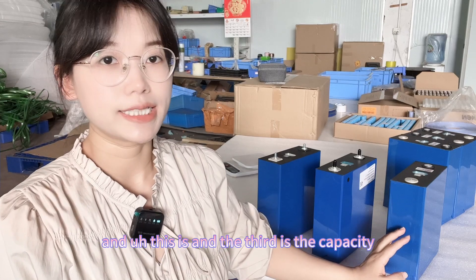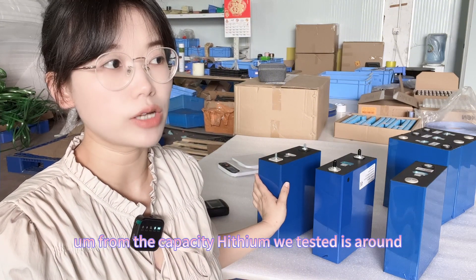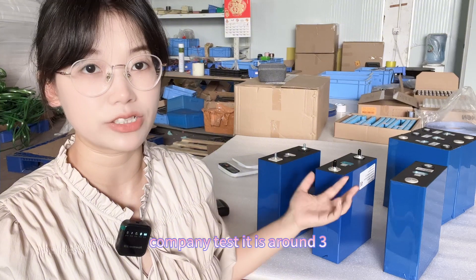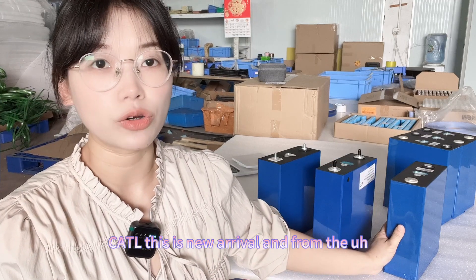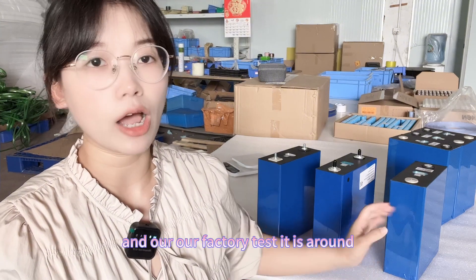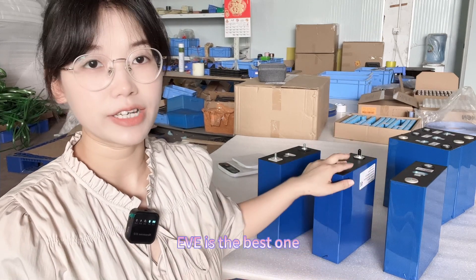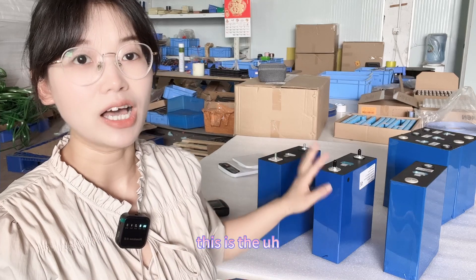For actual capacity, the Hithium we tested is around 295Ah. EVE, from both the testing report and our company's test, is around 310Ah. For CATL, this is a new arrival, and from the testing report and our factory test it is around 299Ah. So from capacity, EVE is the best, followed by CATL, then Hithium.